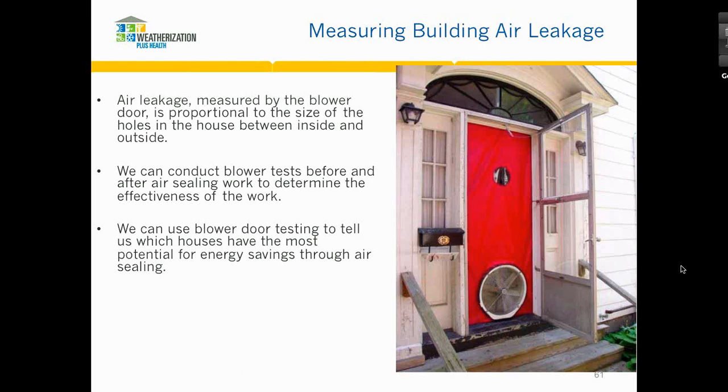And then we get into the building envelope testing. Bob mentioned this. We look for the air leakage. This is a picture of a blower door if you haven't seen one before. It's basically a tarp that fits into the door really tightly with an adjustable frame. And then this here is a powerful fan that you hook up to a manometer, which measures pressure differences at really minute levels.